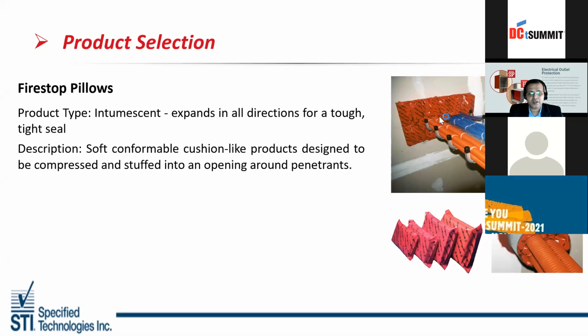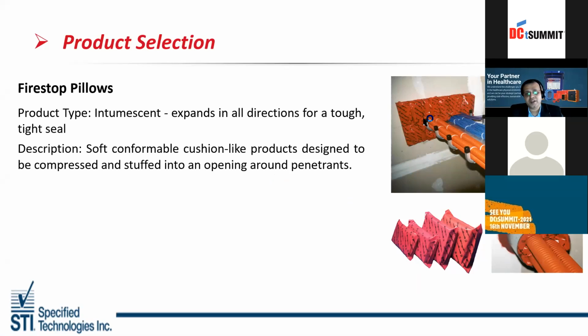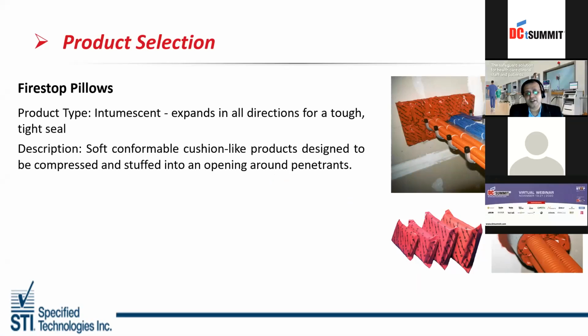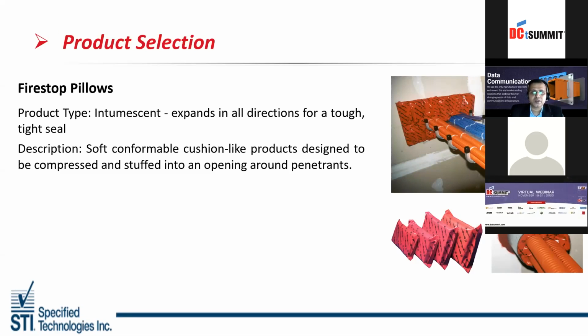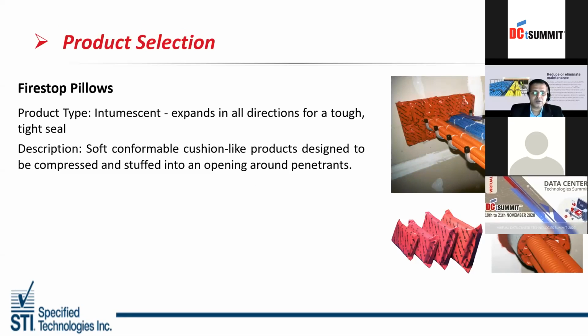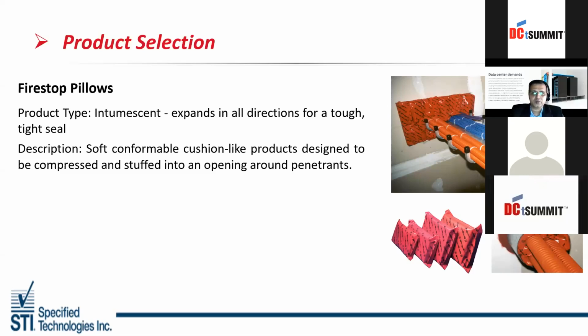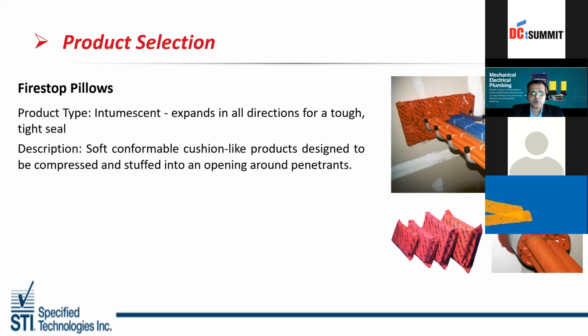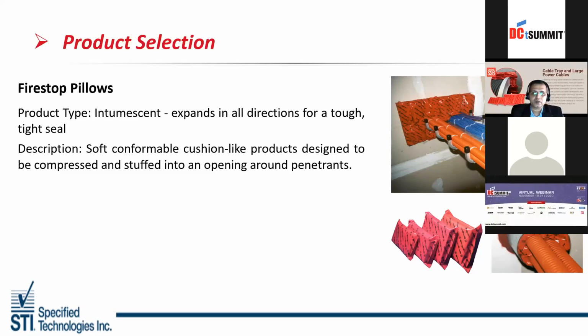In case of fire, this will expand 15 times. One single pillow will expand 10 to 15 times its volume, and it will crush and close the area. Now in this, if you see towards your right hand side top, the three sleeves that have been installed, one is empty. The empty one is also fire stopped using this pillow. It's a metallic sleeve, and this pillow has been installed here.